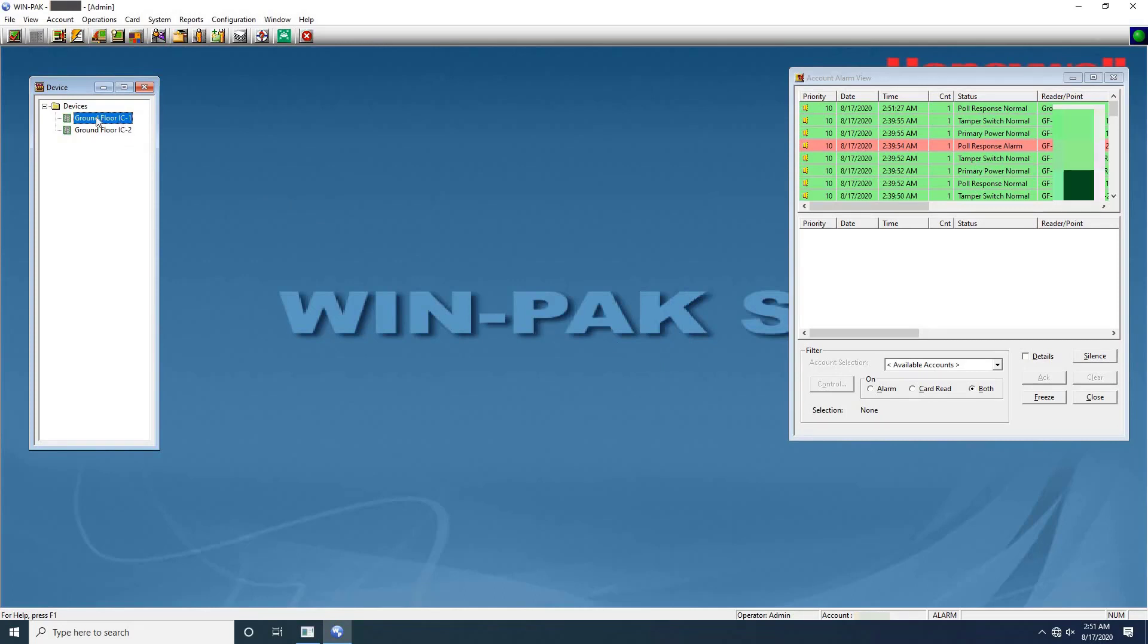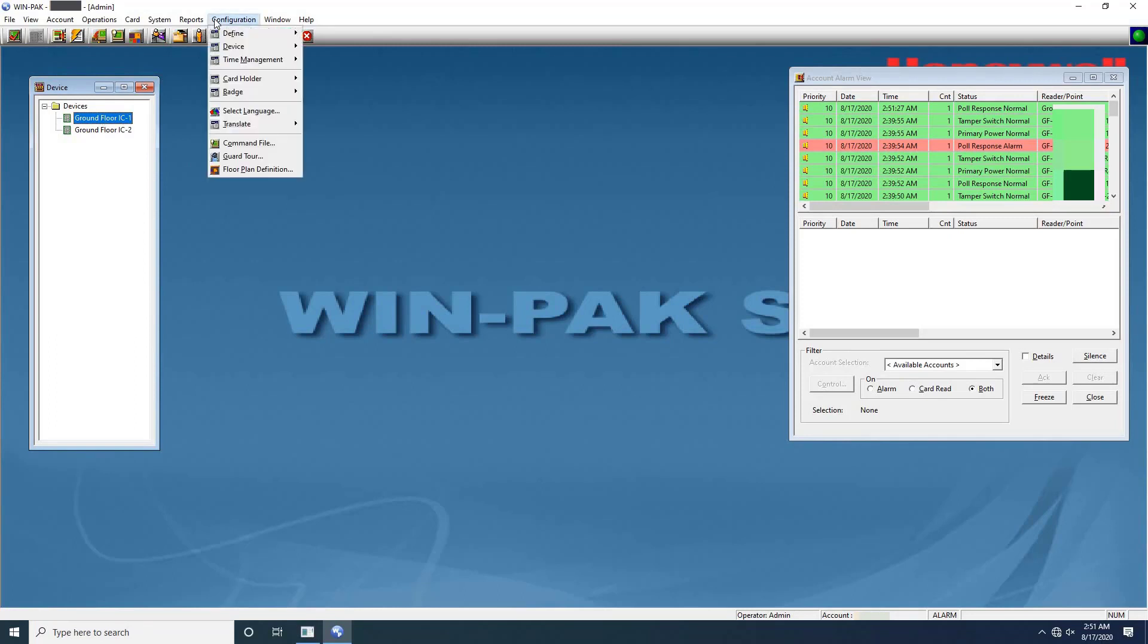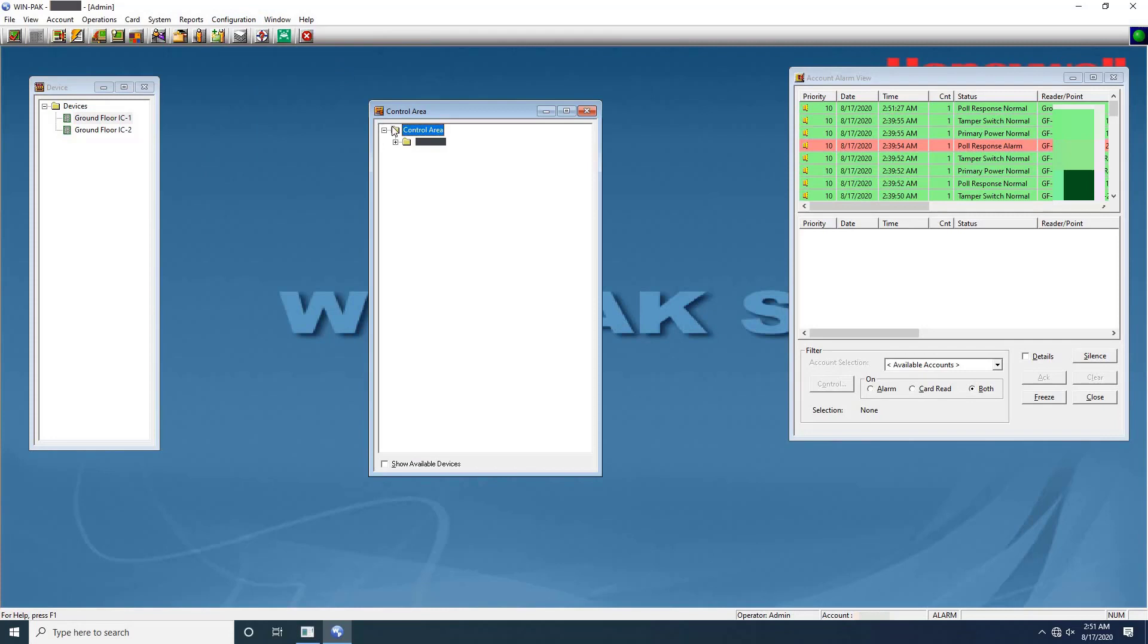Now let's define the control area. Go to Configuration, then Define, then Control Areas. The control area window will appear. Control areas are logical areas containing devices such as loops, panels, input points, output points, groups, and readers. Control areas are defined by creating a control map of the devices and adding them to a tree structure. This map shows the status of each device, the set of actions to be performed for the device when an event takes place, and the relationship between the various devices.